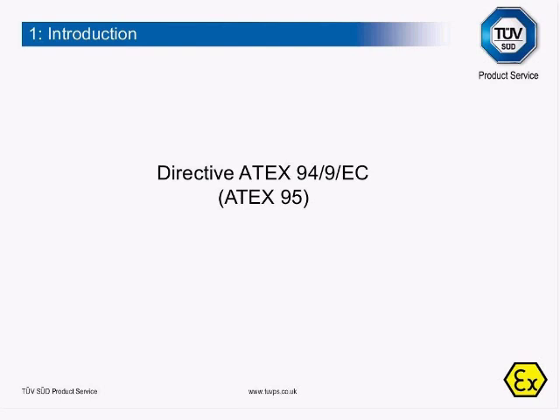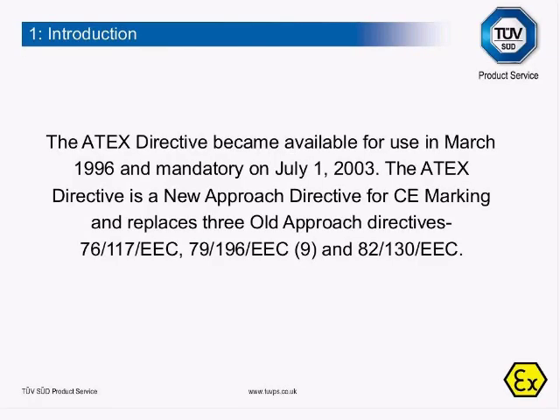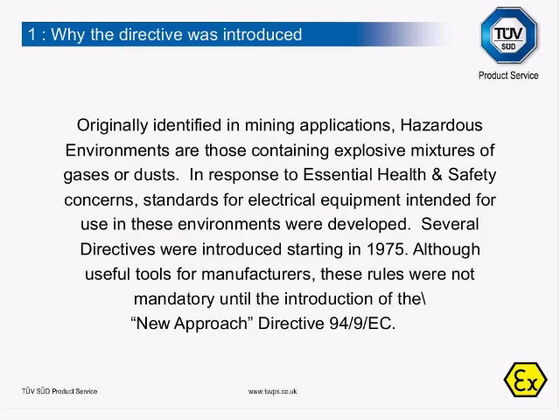The ATEX Directive, or the Product Directive 94/9/EC, also called ATEX 95, became available for use in March 1996 and mandatory on July 1, 2003. The ATEX Directive is a New Approach Directive for CE marking and replaces three old Approach Directives. Originally identified in mining applications, hazardous environments are those containing explosive mixtures of gases or dust. In response to health and safety concerns, standards for electrical equipment intended for use in these environments were developed. Several directives were introduced starting in 1975 and were useful tools for manufacturers, but these rules were not mandatory until the introduction of the New Approach Directive.